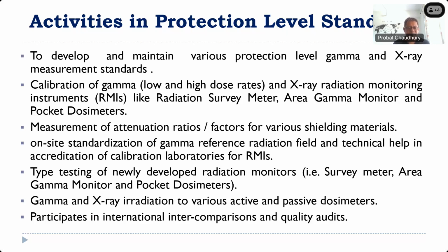Then another aspect is type testing. Lots of developments are being carried out in radiation monitoring instruments. People are developing radiation monitors like survey meters, area gamma monitors, and pocket dosimeters of different designs and different types of detectors. For whosoever develops such an instrument, type testing of these monitors can be carried out in the radiation standards lab here for all the ranges as well as all the other aspects. This is very important because type testing can cover the entire range and give you the exact results. Only then can it go for manufacturing of the equipment.